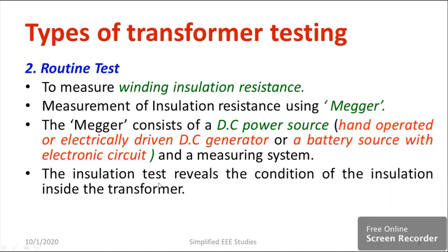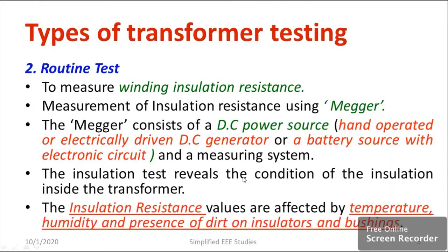Whichever you find convenient, you can use either type. The insulation test reveals the condition of insulation inside the transformer. The insulation resistance values are affected by temperature, humidity, and presence of dirt or moisture. We have to compare with the standard value of insulation resistance — it should not be less than the minimum value. If you find the insulation resistance is very low, you can understand some problem has occurred in the winding and you need to replace the winding insulation.